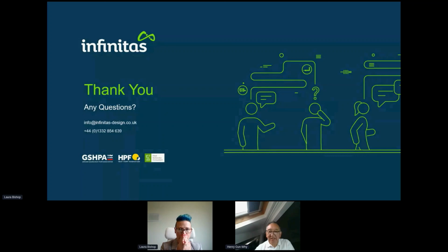Yeah, that's okay. You mentioned in your presentation about thermal storage. Can you give some idea of the size of thermal storage needed to provide a sufficient buffer for systems to work? Yeah. Some heat pumps will need a minimum volume on the condenser side. That's really important to understand to start with, because that's your minimum thermal storage size. And of course, if you've got pipework going into a heat network, that might give you enough volume, so you may not need a thermal store. You don't always need a thermal store with a heat pump.